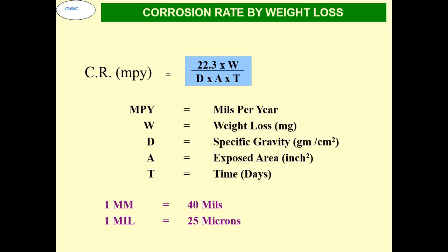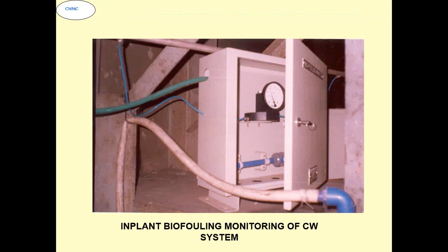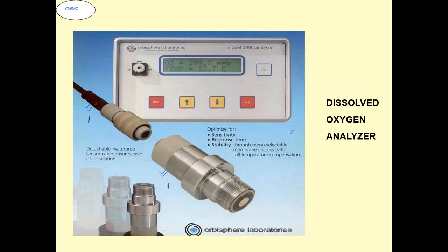This is how we calculate the corrosion rate from the coupons. Typical biofouling monitor based on differential pressure, but I have my own doubts. I have never seen it working at any place. But most chemical suppliers will have this differential pressure biofouling monitor. Dissolved oxygen analyzer.